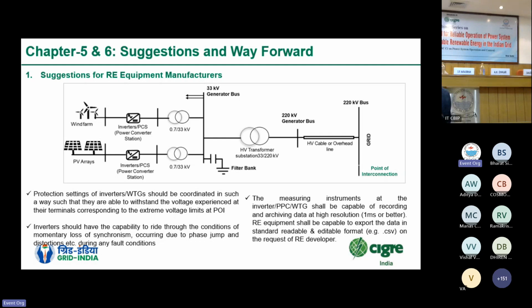So a recommendation was given that protection settings of inverters and WTGs should be coordinated in such a way that they are able to withstand the voltage experienced at their terminals corresponding to the extreme voltage limits at the POI. So this behavior is desired for the voltage levels at the point of interconnection. Their equipment should be tuned accordingly, so that when the voltage at the point of interconnection goes to an extreme, the complete set of equipment is coordinated to display that performance.